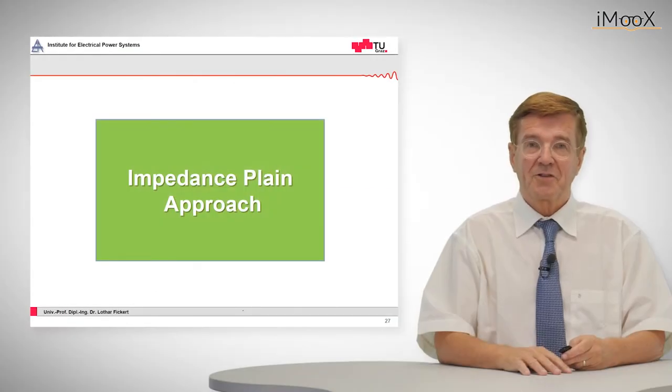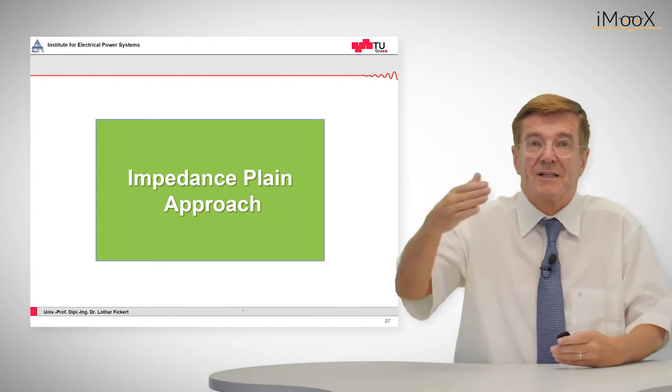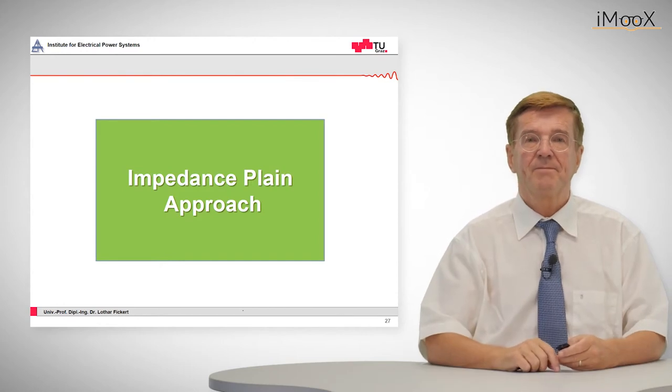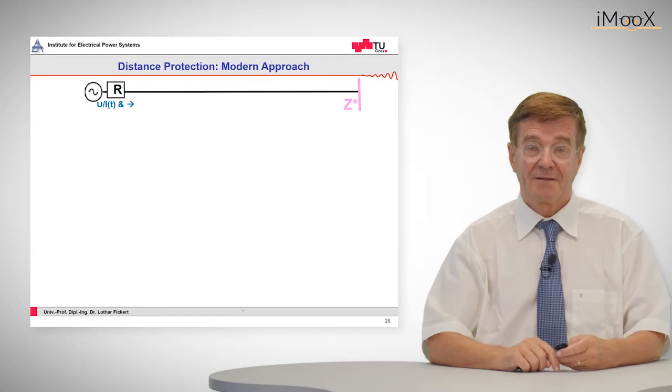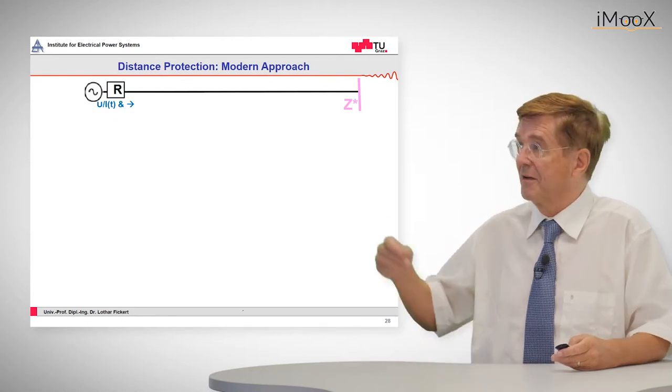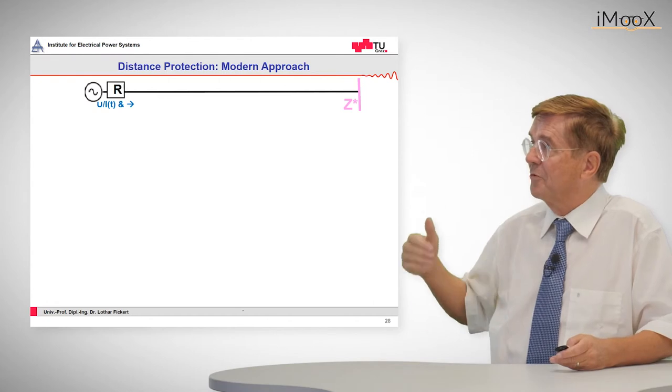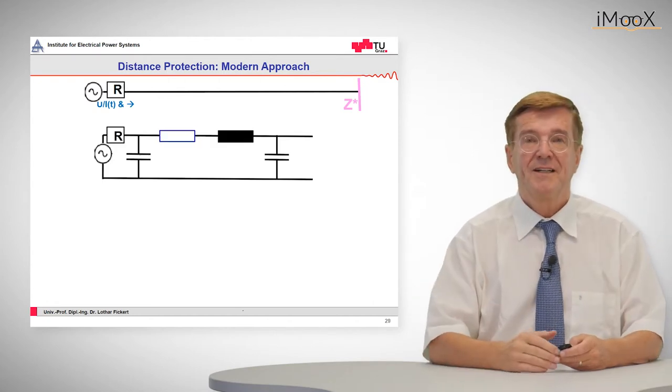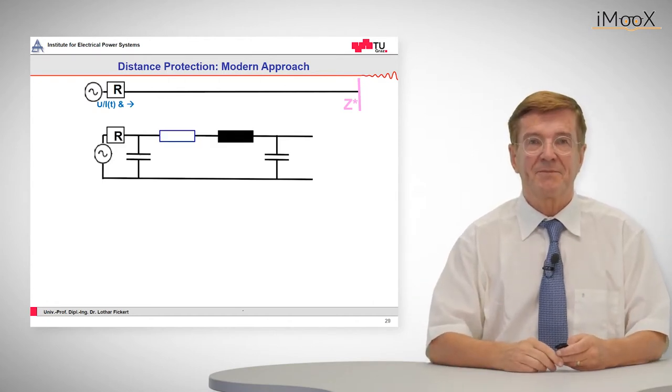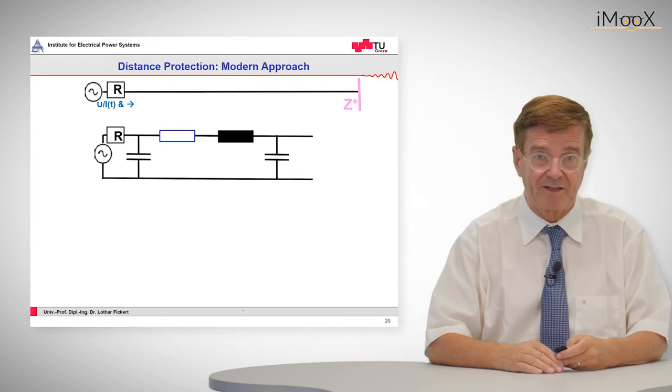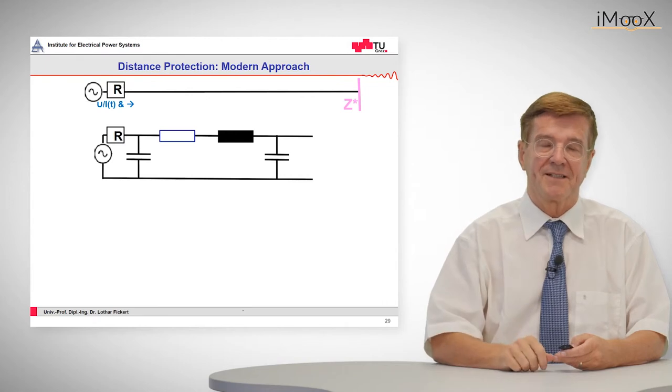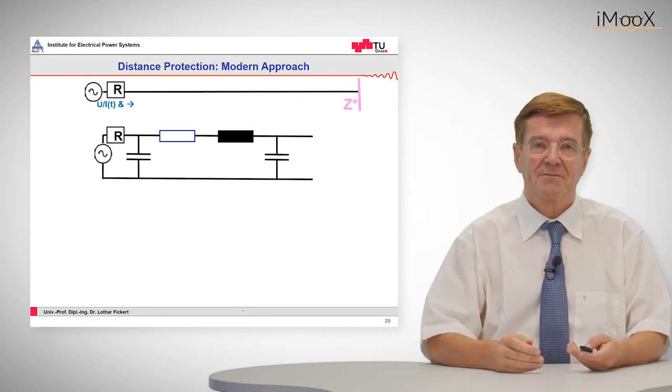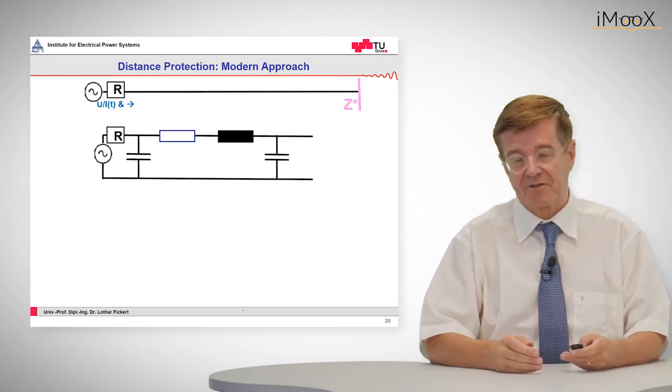The other approach for distance relays in order to determine is the fault on the own line or is it beyond this is the impedance plane approach. So we start again with the same fault impedance model. We have a source, we have the relay and we have a line on which there may be a fault. This line can be represented by the pi equivalent circuit which consists of a resistance and inductance and two capacitances which usually are assigned to the left and to the right side.